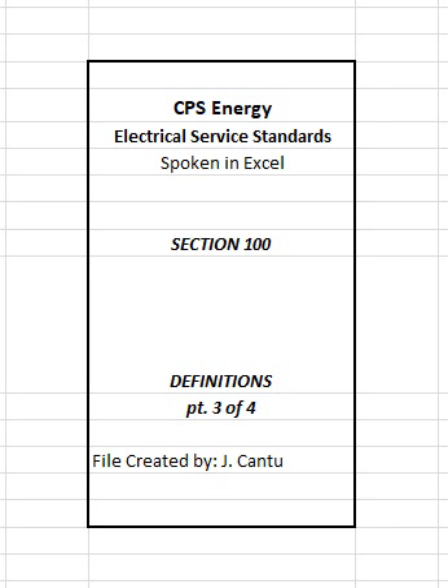Parallel operation. Parallel operation is the operation of two or more sources of AC electrical power whose output leads are connected to a common load. Connection of the power sources is made so that the sources electrically function as a single source of power. Parallel operation requires that the two sources of electrical power must match in voltage, frequency, and number of phases. Point of common coupling. From the perspective of the distributed generation, DG, this is the nearest point on the CPS Energy system where other customers can be connected. This is generally the point where system voltages and harmonics are metered, as it best represents the DG's impact on other customers on the CPS Energy system.